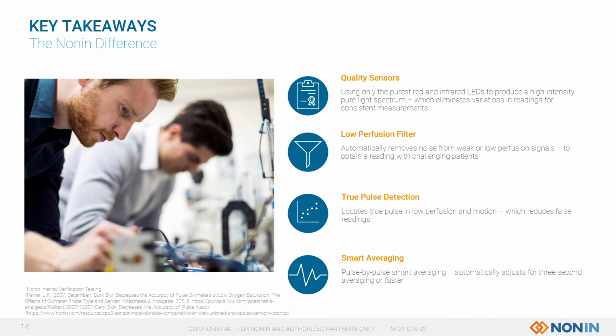And Nonin's PureSAT technology also features true pulse detection, which reduces false readings by locating the true pulse in low perfusion and motion. And this eliminates false readings due to patient motion, reducing the time required to obtain a reliable measurement. And what we mean by reliable is a measurement that is consistent, trustworthy, and in good quality. It is also FDA cleared for plus or minus 3% SpO2 accuracy in motion.